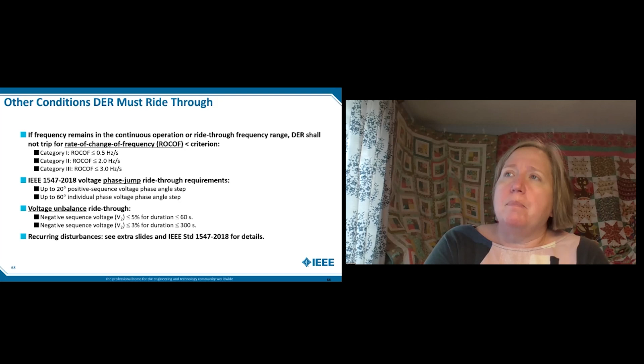So there is a concern about ride-through versus island detection. There are enough voltage trips, both undervoltage and underfrequency trips. Distribution faults can depress the voltage on the phase that the fault is on. So you will get some DER tripping, and then you mess up the generation-to-load balance, which will prevent the island from sustaining. There's still a requirement for DER to detect and cease to energize within 2 seconds, for all generation-to-load conditions.